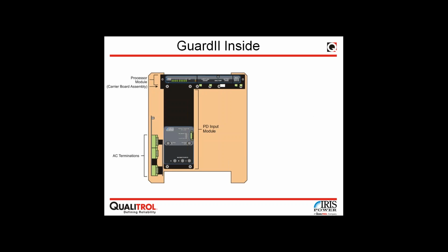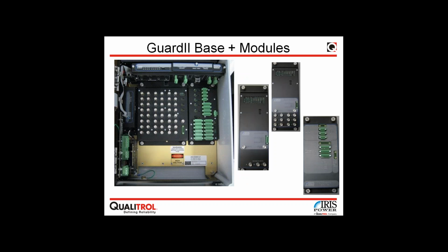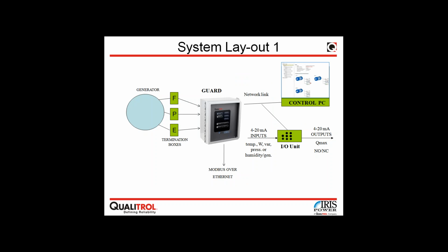Inside, we will have a sort of motherboard where the plug-in modules will be connected. One module will be dedicated to partial discharge monitoring, and the other module will be dedicated to other technologies, and they can be different depending on the choice of module. Again, the PD module could be different depending on the type or number of sensors, so there will be more or fewer sensors connected. But in any case, this is field upgradable and can be done in service without stopping the machine, as long as the sensors are installed.